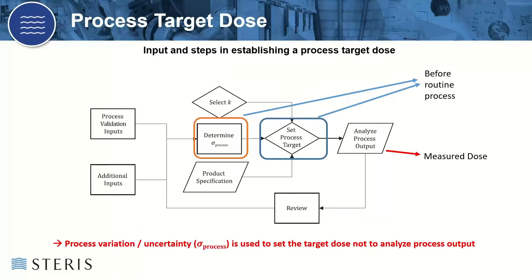We take a look at the inputs and steps in establishing a process target dose. The radiation process is monitored using processing parameters and dosimeter measurements. Three process targets at the routine monitoring position can be defined: a lower target dose, an upper target dose, and a corresponding dose target, respectively to the lower and upper set limits for the process target dose and the actual process target dose chosen for routine processing conditions. There are a number of factors used in determining the range of process target doses, depicted in Figure 1. The key point is that process variation and measurement uncertainty are both used to set the target dose as an input — not to analyze the process output. The output is the measured dose.